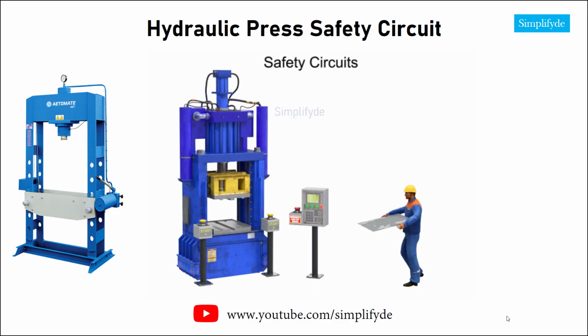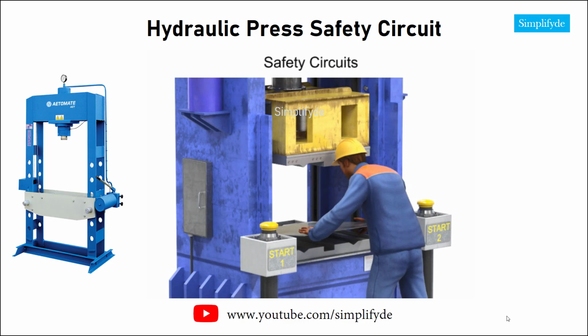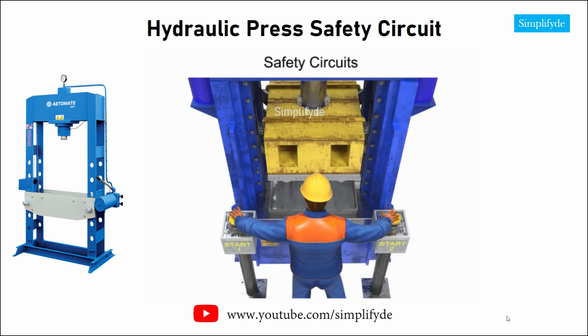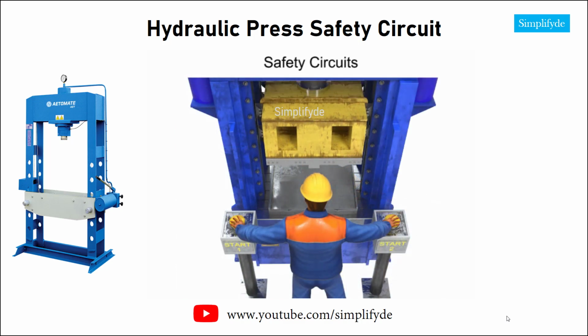When operating industrial machinery, safety is always a primary concern. Two-hand controls and anti-tie-down circuits are safety devices built into the design of electrical circuits that operate industrial machines. Two-hand controls are an actuation device that requires the concurrent use of both hands of the operator to start a cycle. The purpose is to prevent the operator from having any part of his or her body in the work envelope of the machine during its operating cycle.